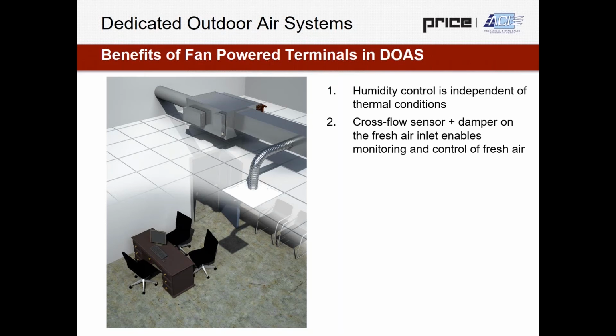Additionally, a large benefit is the utilization of a cross-flow sensor and damper on the fresh air inlet, which enables monitoring and control of fresh air. So this also leads to demand control ventilation and the discussion of adding some extra efficiency by only providing the ventilation air required by the zone. And that's really only possible because of that damper, which can vary that fresh air and monitor that fresh air.